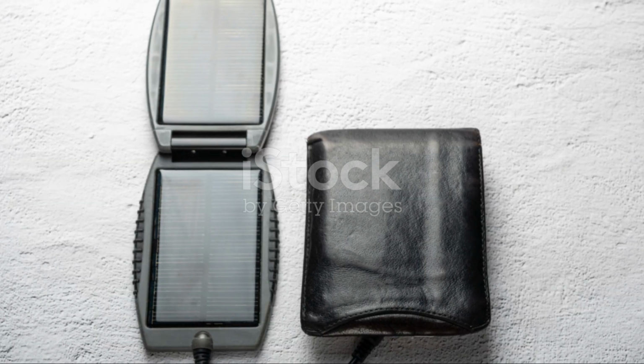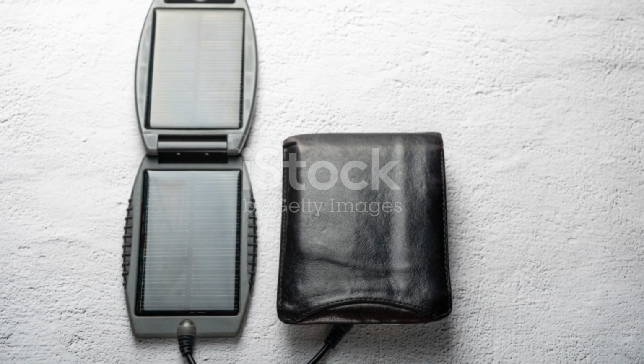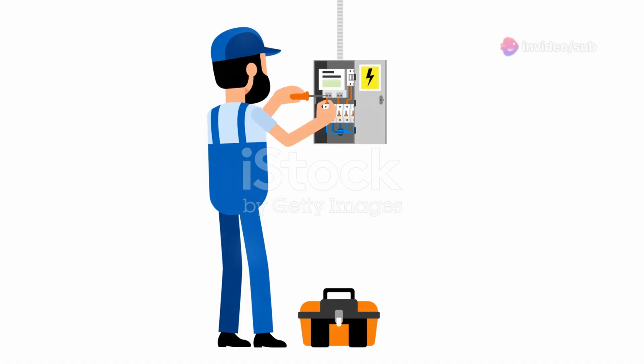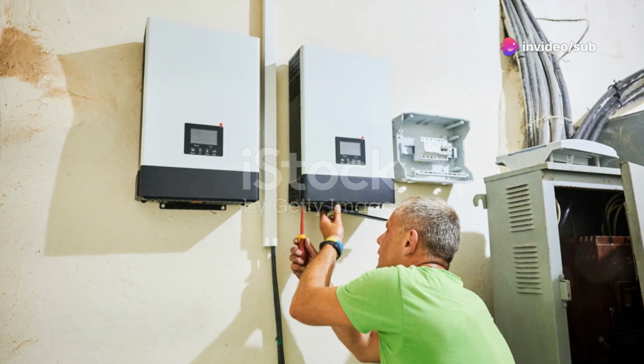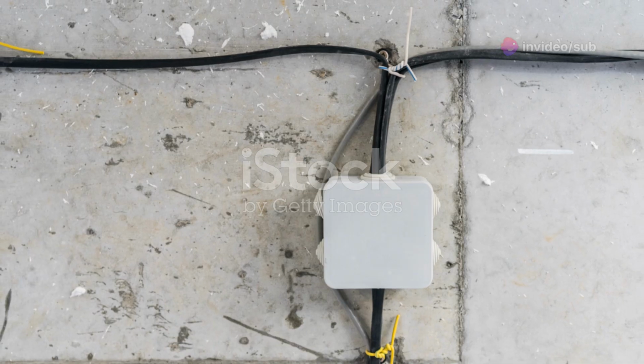Connect the panels together using MC4 connectors or what the manufacturer recommends. Wire panels in series or parallel, based on your inverter's needs. Run the cables carefully to your inverter location. Use weatherproof conduit to protect the wires.